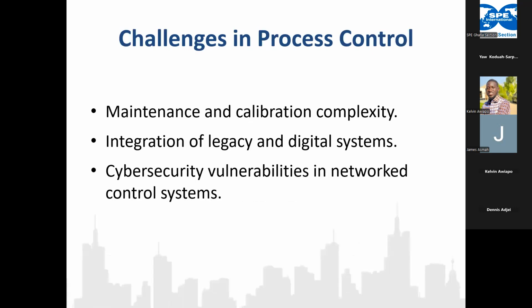Now, the challenges we have in process control, one of it is maintenance and calibration complexity. You may have a big plant that has hundreds of transmitters, and to ensure their reliability, you have to be doing calibration for all of them over time. So you can do preventive maintenance, where you schedule to calibrate all of the transmitters at their specific times. It's a lot of work actually, but it's a way to make the system reliable.